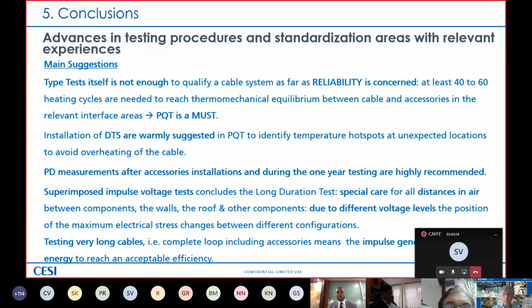Also, long duration test in case of direct current is a must. The installation of distributed temperature sensor are warmly suggested in pre-qualification test in order to identify temperature hotspot at unexpected location to avoid overheating of the cable. PD measurement after accessory installation and during the 1 year testing are highly recommended, both in case you want qualitative information at the beginning and/or quantitative information along the test.